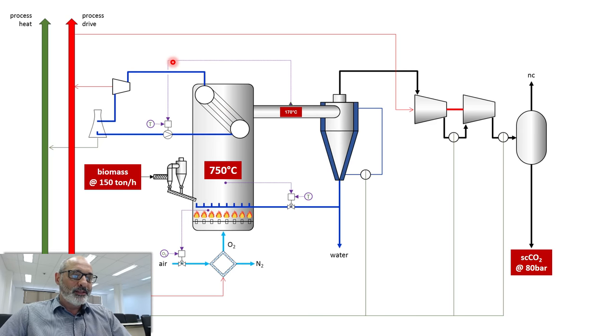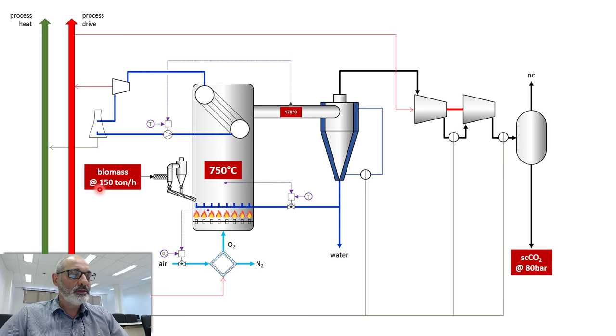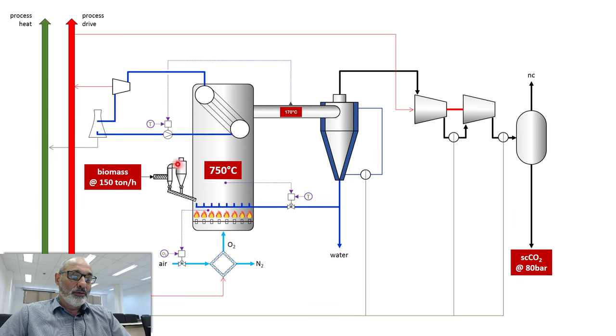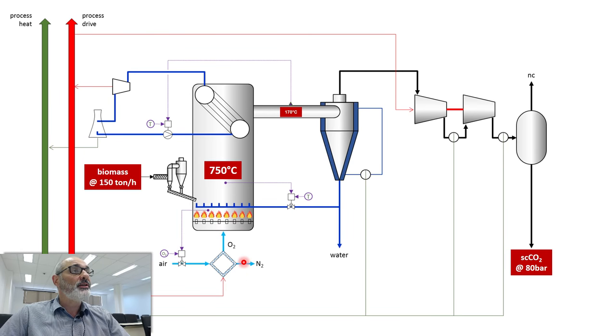We're going to use some typical numbers from a typical sugarcane mill. Suppose we're feeding 150 tons of biomass — that's the fuel. We have to calculate the amount of exergy that these 150 tons are carrying, in terms of exergy. So we're feeding 150 tons per hour of biomass to the boiler. This is actually an oxy-fuel boiler, so we have to include an oxygen separation process, which also uses exergy.